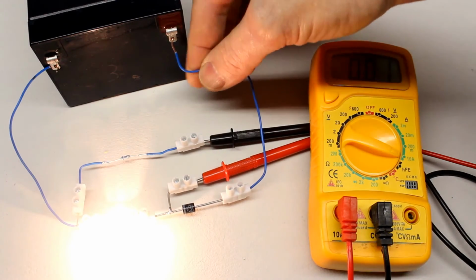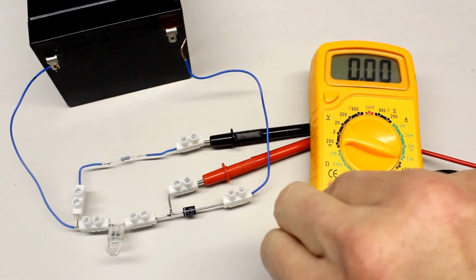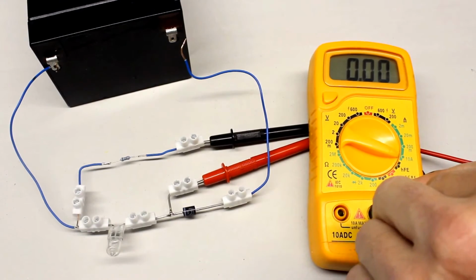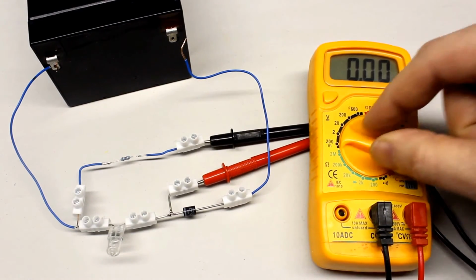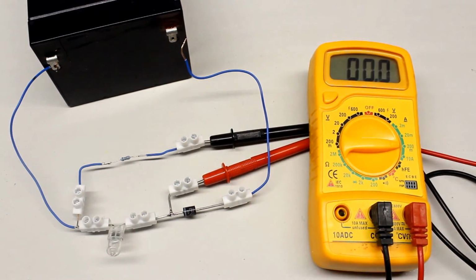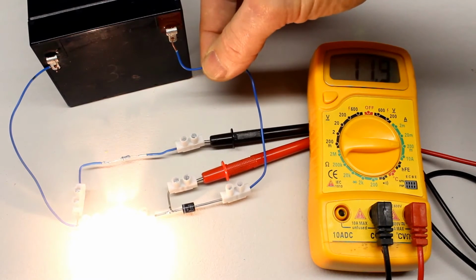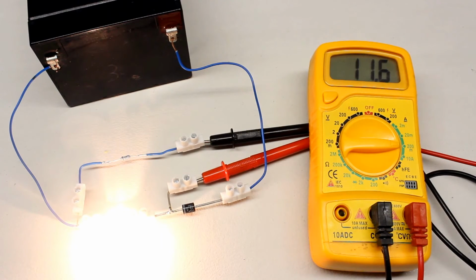In order to enable the lower range, the red test lead has to be removed from the left and reinserted in the right jack, and the rotary switch has to be set to the 200 mA range. After reconnecting the circuit to the battery, we get 11.6 mA. Thus we can step down to the 20 mA range.